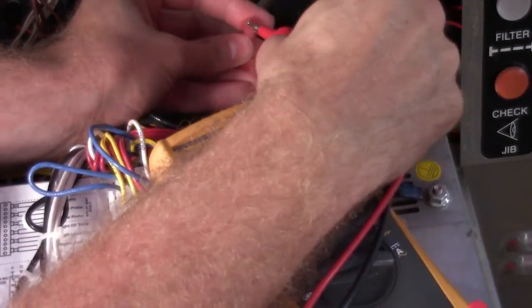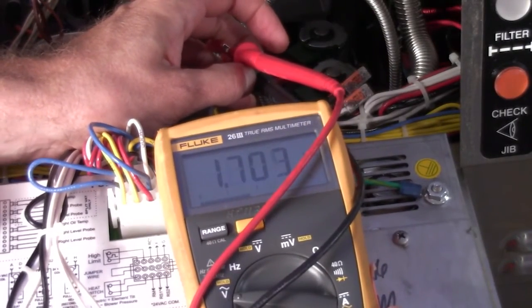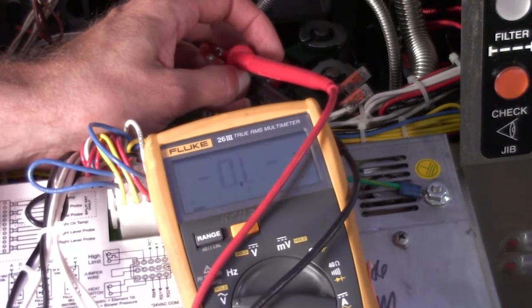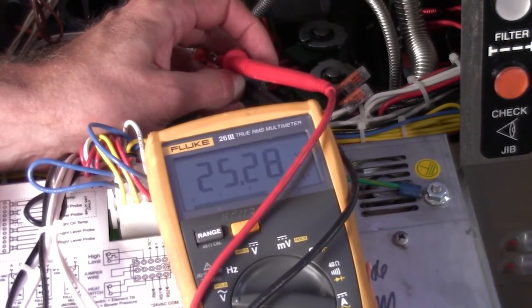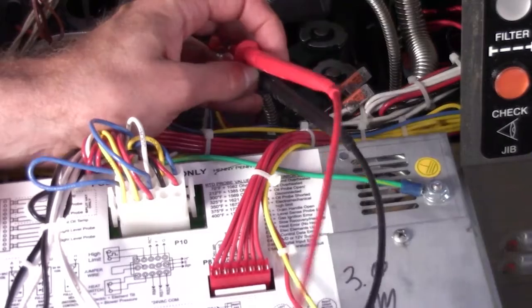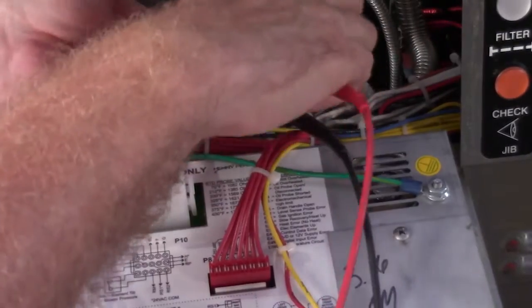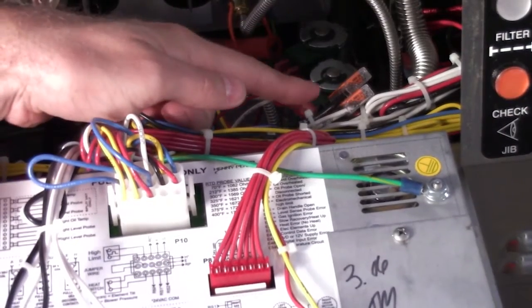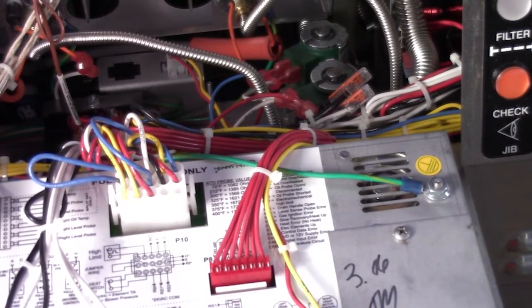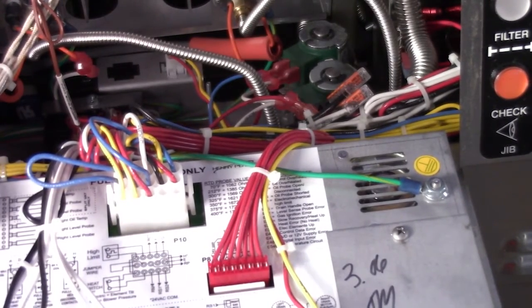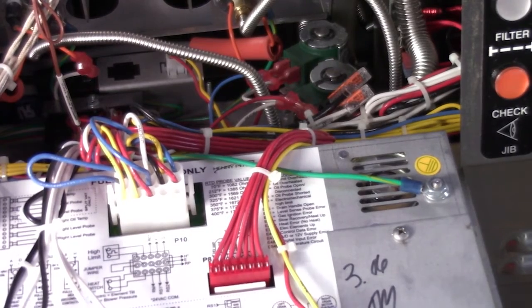Get this to stay, it's not going to stay. Put my leads in there, wait for it to call for heat. It calls for heat, and I'm getting a good voltage, 25 volts out to it. So now I could go ahead and check to see what's going on then, possibly with my solenoid to my main burn on my gas valve. Now what I can do is ohm it out, comparative ohms to check the resistance, which we're going to do up on the workbench.